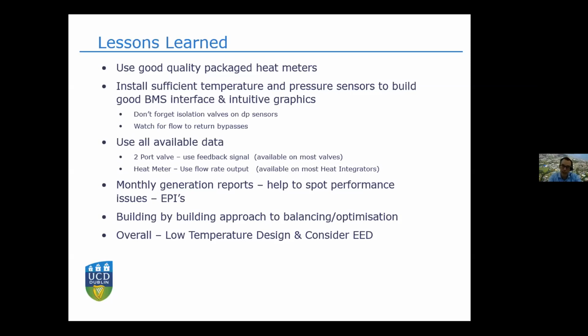Heat meters also generally have a flow rate output which isn't always tapped into - it can be an analog pulse or whatever. By using that data you can build a great system graphic, and having a good system graphic lets you see what's going on in your system, where the heat or flow is going, and whether it's going where you want it.